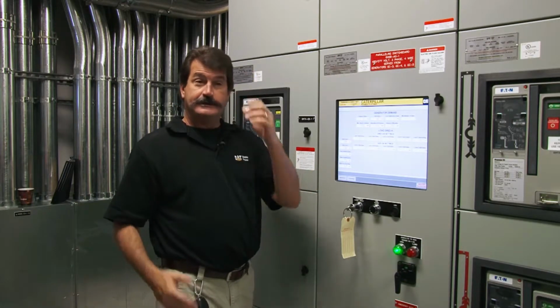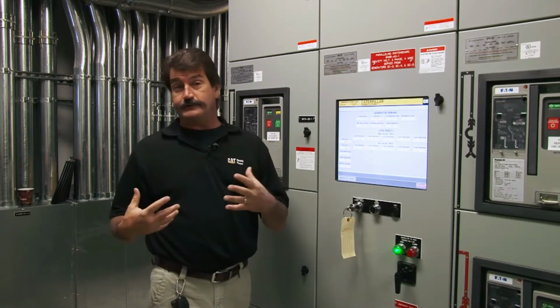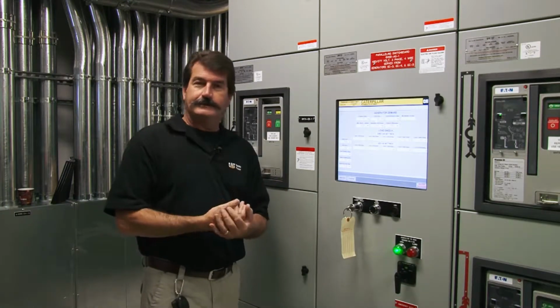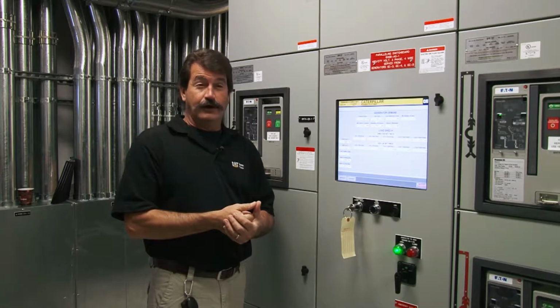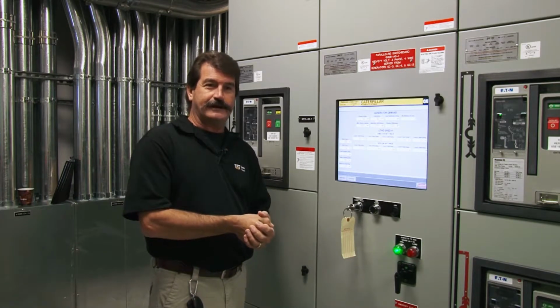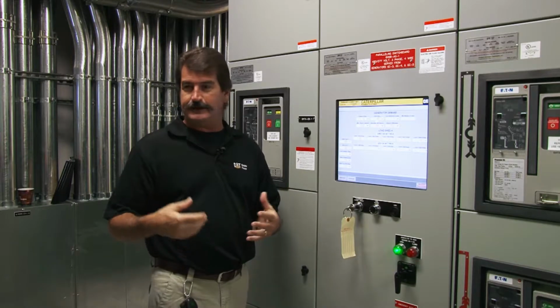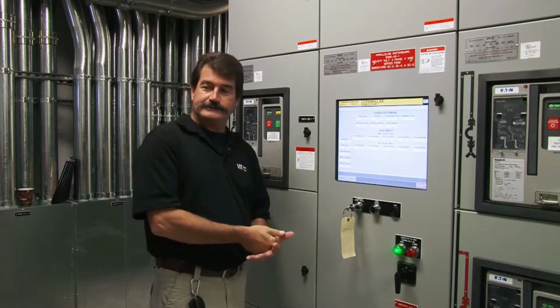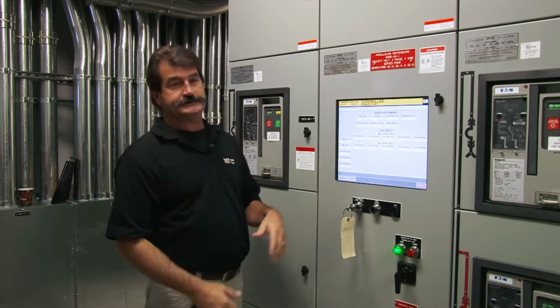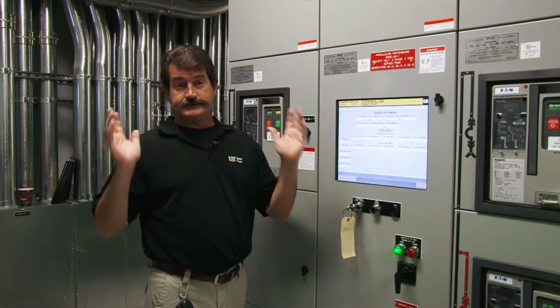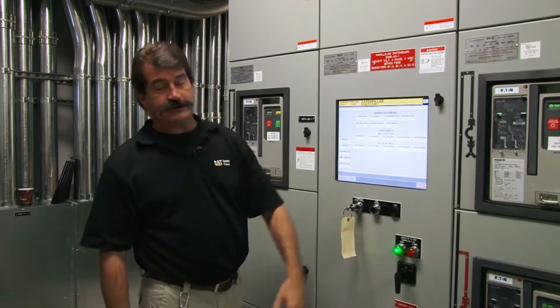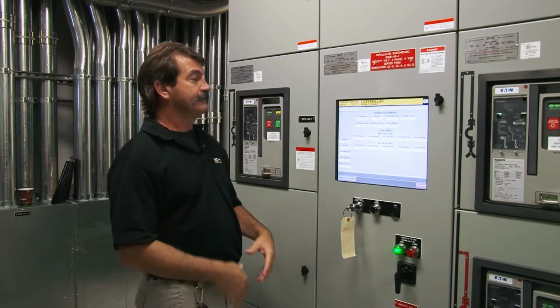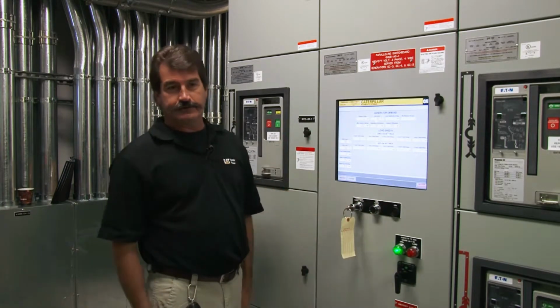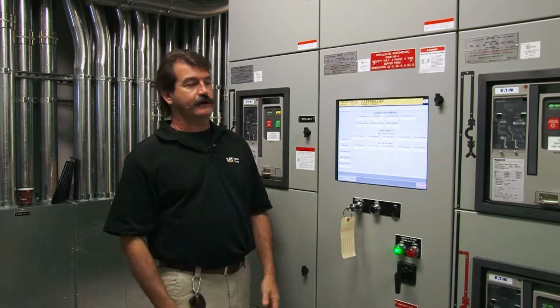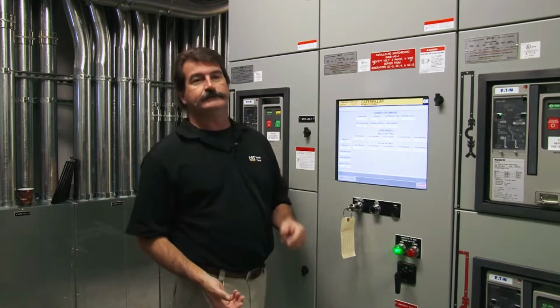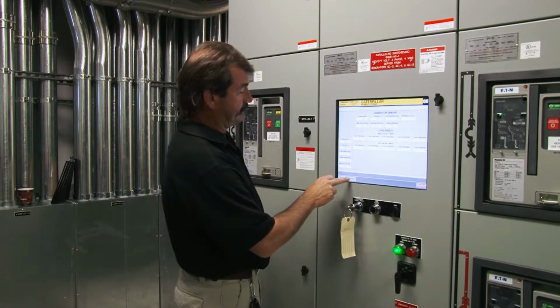If your gens drop to 55 hertz, and that's all your gens, right? So if you've got a big load or something that's dragging those things down, maybe you only had 2 gens come up and everything's hitting and it's dragging them down to 55 hertz for 3 seconds, it's going to open up every distribution breaker you have, every breaker that's going out there. It's trying to unload those gens so they don't shut off. And then you're going to have to show up and reset that.